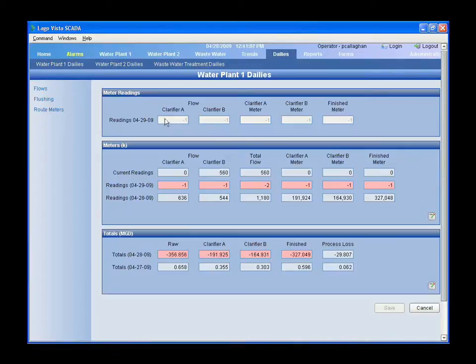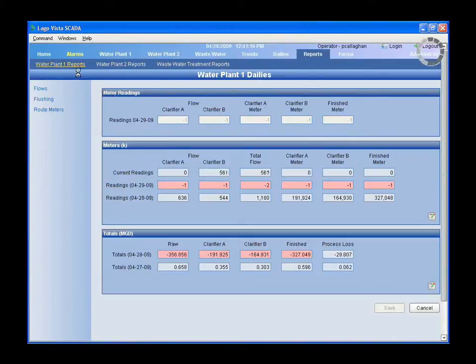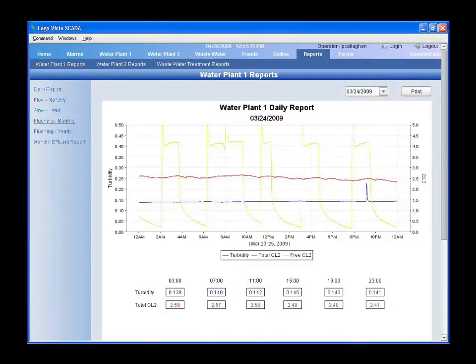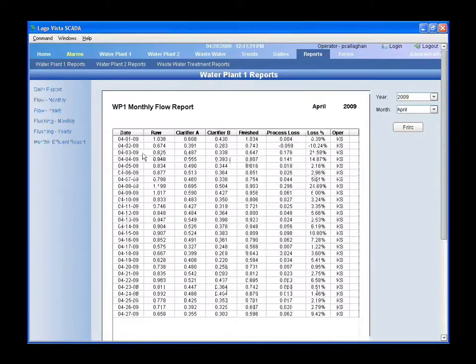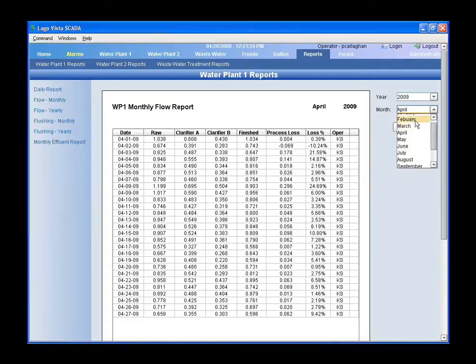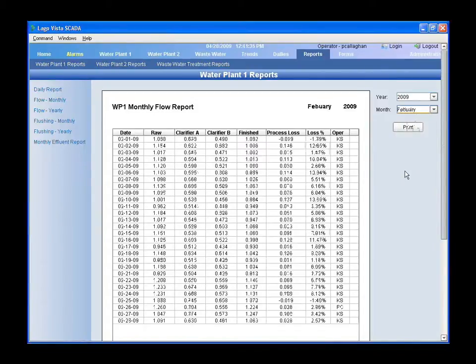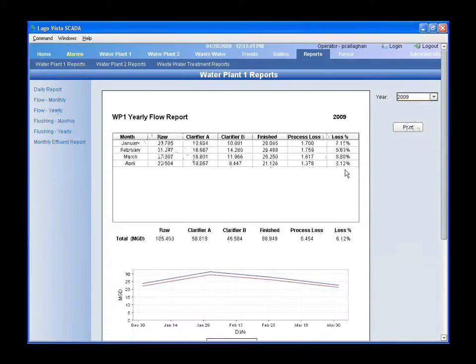Operators come in and record the actual meter numbers into the system. Since it's stored in a database, I can pull up reports — like if they want to know what the monthly flow was, here it is. They can see how much raw water they were taking in, how much finished water they were creating, and what was their process loss. They can go back into whatever month they want and pull up the data, or do yearly reports comparing this year or last year.